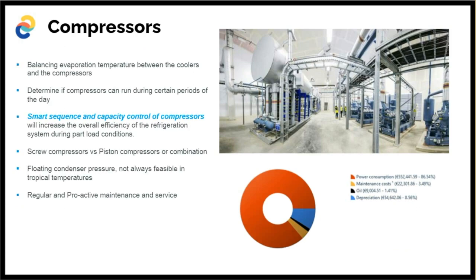Now, what can we do on these compressors? First of all, it's balancing the evaporation temperature between the coolers and the compressors. Do we invest in cheap coolers, smaller coolers? But then we have to bring the evaporation temperature down, and that means bigger compressors. The other way around, if we have big coolers, then we could use smaller compressors. So it's a balancing act. As I said before, what times of the day the compressors can run, and certainly a smart sequence and capacity control system.